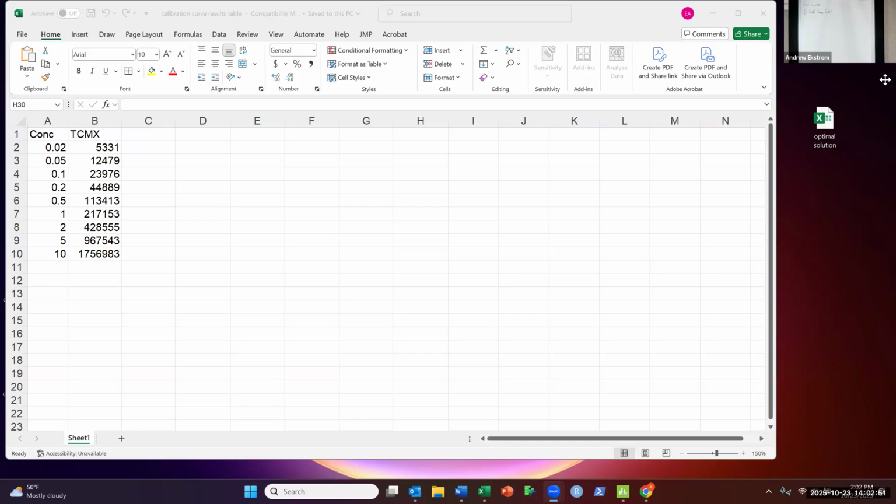If we're talking about a calibration curve, I'm just going to pretend like a calibration curve is linear for a moment. So let's say that's the curve that we're looking at. If you start measuring things that are out here or way out here, what ends up happening is you have essentially a 95% confidence interval that's going to look something like that.